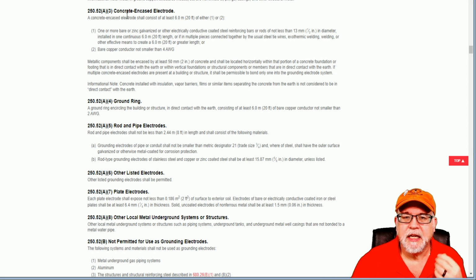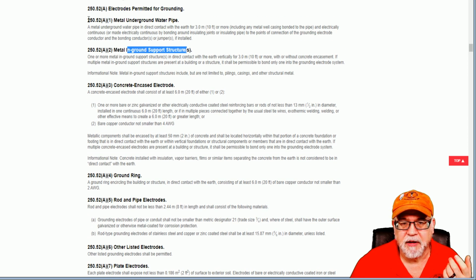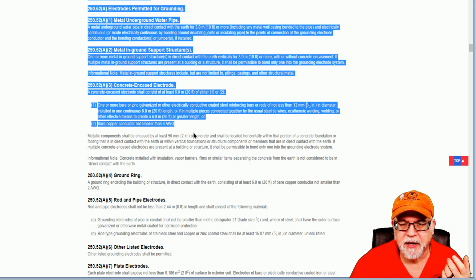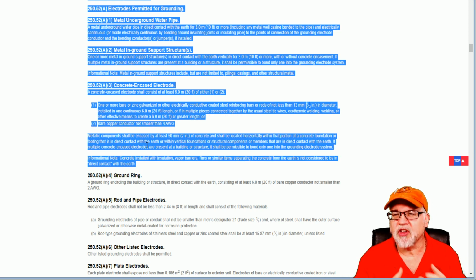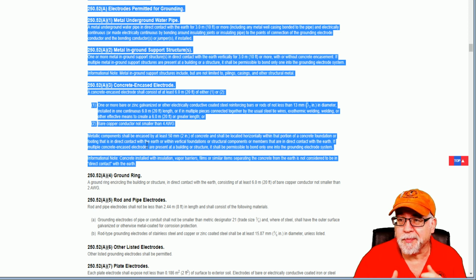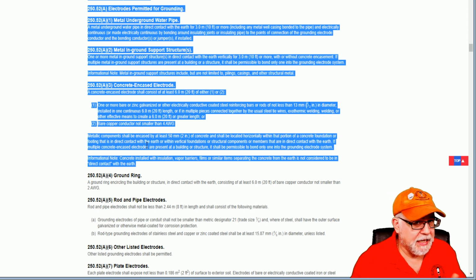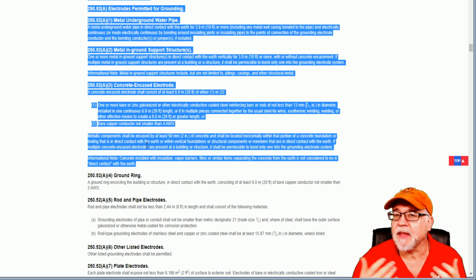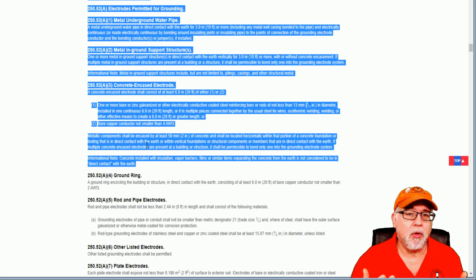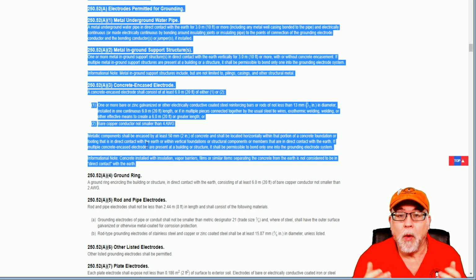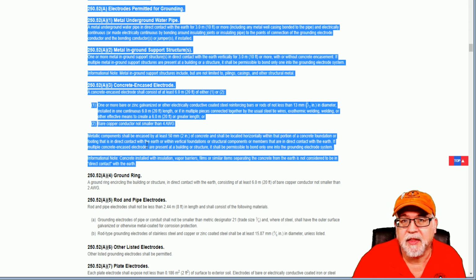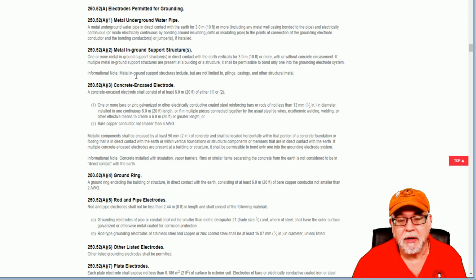Now, one thing you'll notice is (A)(1), (A)(2), and (A)(3), these three right here, are pretty inherent to construction, right? The water pipe ground is something that's out of your control as the electrician. That's put in by the plumbing or the utility coming to the building. We don't really control that. The in-ground support structure is all based on the construction of the building. We don't control that. As an electrician, I want to be keenly aware of that. Why? Because if that's already in place, then that makes my job a lot easier. I've got to make a connection to it, but other than that, my grounding electrode system is done. So again, it can make my job easier.